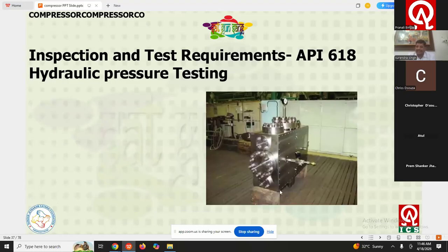In this picture, you can see that this reciprocating type compressor is under hydraulic testing. The gauge is mounted and then pressurization is done. This is a typical picture, and the holding time may be from 1/2 to 4 hours depending upon the customer as well as API requirement. API 618 states that the pressure holding time shall be 30 minutes, but the customer can give their own requirement, which may be more stringent. So first see in the QP what time is written for holding the pressure.